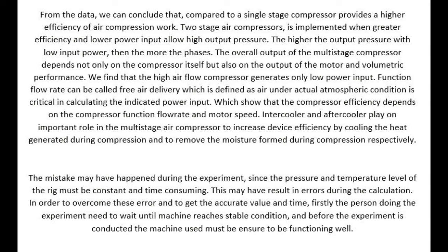The intercooler and aftercooler play important roles in the multi-stage air compressor, to increase efficiency by cooling the heat generated during compression and to remove the moisture formed during compression respectively.